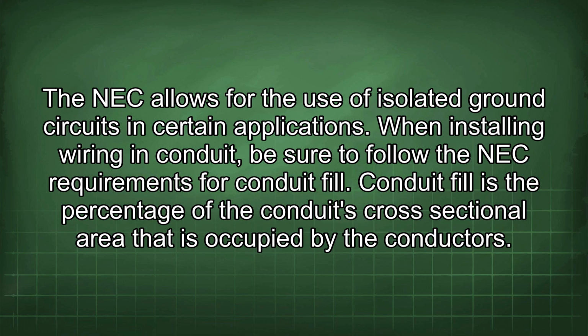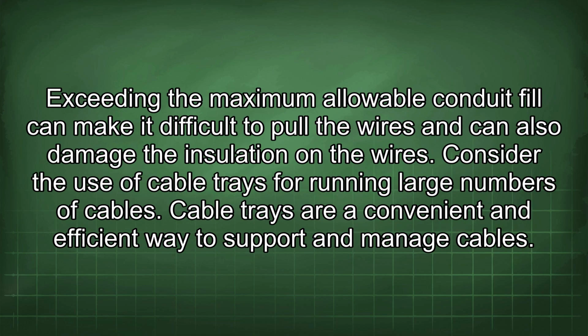When installing wiring in conduit, be sure to follow the NEC requirements for conduit fill. Conduit fill is the percentage of the conduit's cross-sectional area that is occupied by the conductors. Exceeding the maximum allowable conduit fill can make it difficult to pull the wires and can also damage the insulation on the wires.